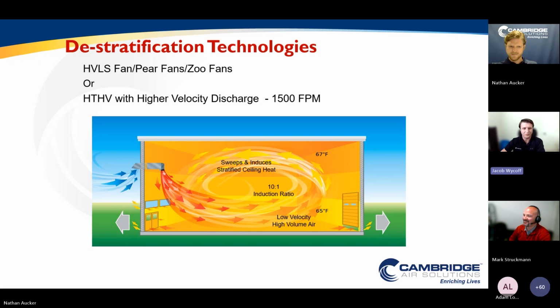It's going to discharge the air at a 45-degree angle. It's going to sweep that air across the floor, hit that back wall, with throws of anywhere from 250 to 275 feet. It's going to hit that back wall, turn, and sweep and induce that stratified ceiling heat as well. So we often see a 10-to-1 induction ratio with these pieces of equipment, meaning for every CFM of air that the supply fan of the HTHV unit provides, it's moving 10 CFM of air that was already in the facility and mixing that air throughout the facility.